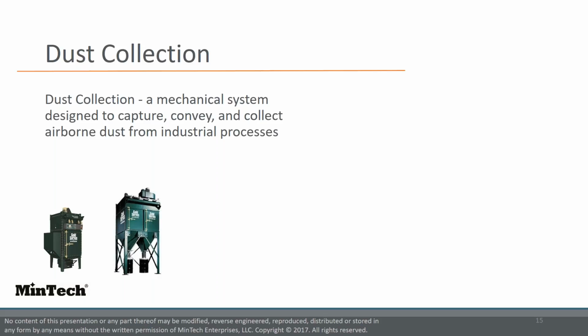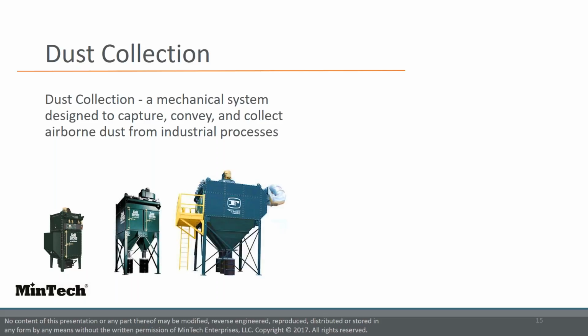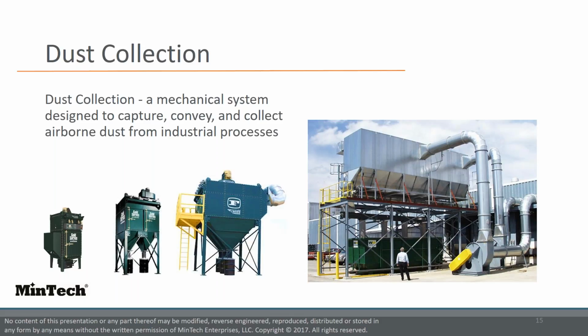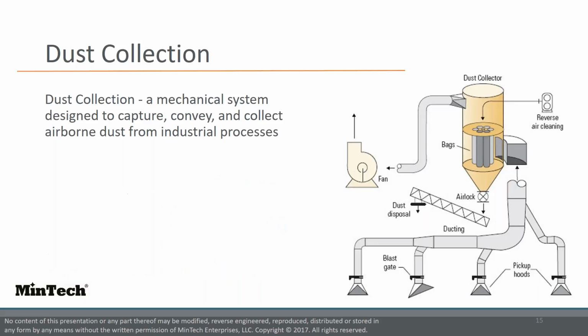Dust collectors may be single unit designs or a collection of devices used to separate particulate matter from the process air. They come in a wide variety of sizes and designs, from small units made for small workshops to large units that can measure hundreds of feet long and several stories high. Dust collectors are often used to recover valuable granular solid or powder from a process stream, and they can be employed to remove granular solid pollutants from exhaust gases prior to venting to the atmosphere. There are many applications of dust collection where they are the best available technology, and dust suppression is simply not feasible.